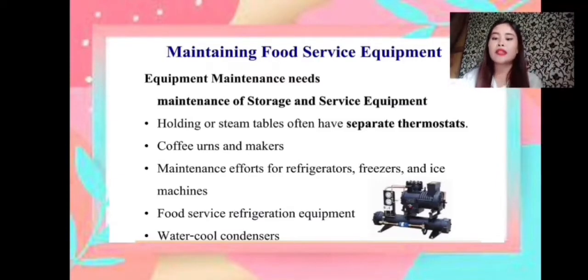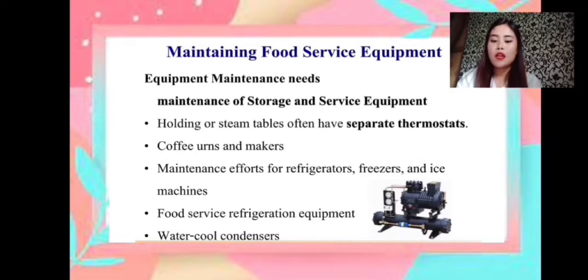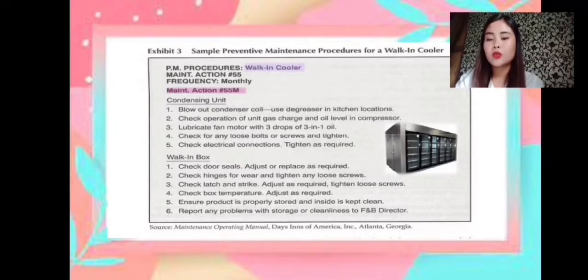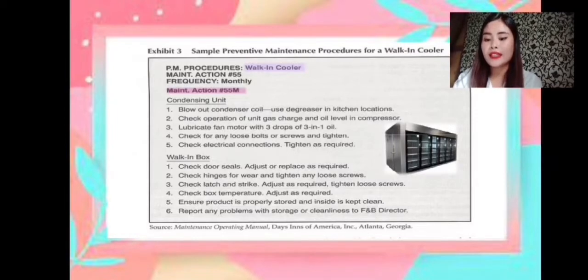Maintaining food service equipment — equipment maintenance needs for storage and service equipment: holding or steam tables often have separate thermostats, coffee urns and makers, maintenance efforts for refrigerators, freezers and ice machines, food service refrigeration equipment, and water-cooled condensers. Here is a sample preventive maintenance procedure for a walk-in cooler. Condensing unit: 1. Blow out condenser coil and use degreaser in kitchen locations. 2. Check operation of unit, gas charge, and oil level in compressor. 3. Lubricate fan motor with 3 drops of 3-in-1 oil. 4. Check for any loose bolts or screws and tighten. 5. Check electrical connections and tighten as required.